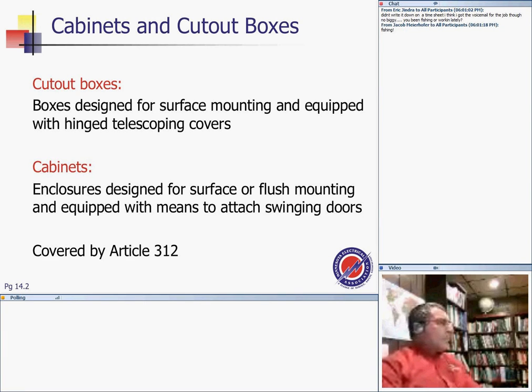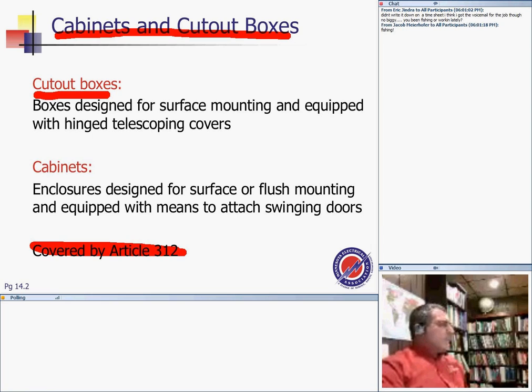Now, cabinets. We talked about cutouts and cabinet boxes, guys, but this is one that we covered last week. Since we have boxes, just to throw this in, this is what we covered last week: boxes designed for surface mounting and equipped with a hinged cover. So if you hear a cabinet or a cutout box, this is not a J box, not a pull box, not a device box for the most part, and it's meant to enclose an overcurrent protection device.